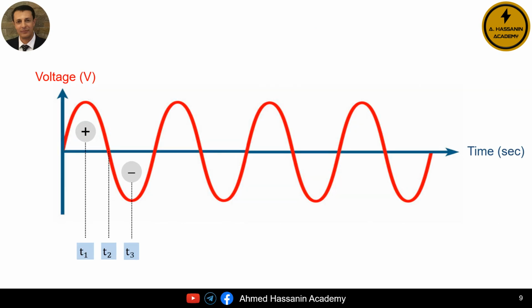And in order to understand what it means for the magnetizing inrush current to be a random phenomenon, and why it does not necessarily occur every time we energize the transformer, we must first review and understand some very important points. Of course, we all know that the network voltage is alternating voltage or alternating current, which means that the voltage value is always changing. In other words, the value of the network voltage at moment t1 might be a positive value, the value at moment t2 might be 0, and the value at moment t3 might be a negative value. Therefore, we can understand from this that the value of the network voltage is constantly changing at every instant, whether it is a positive value, a negative value, or 0.